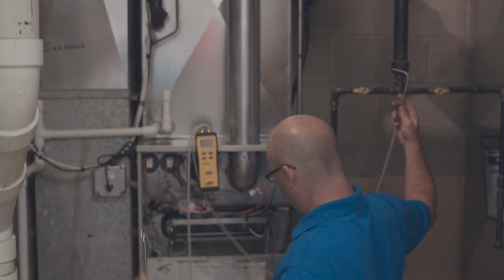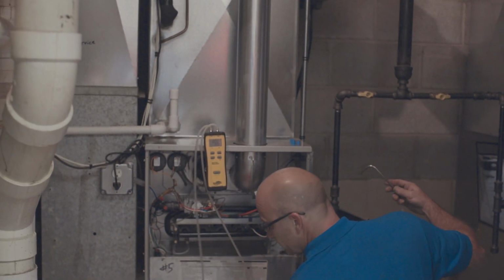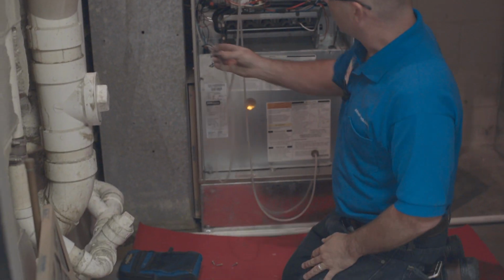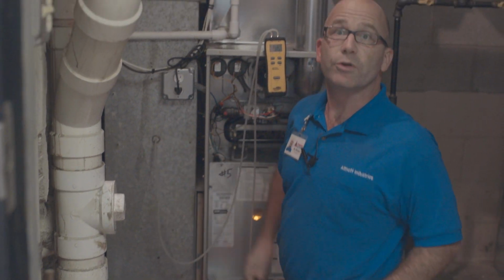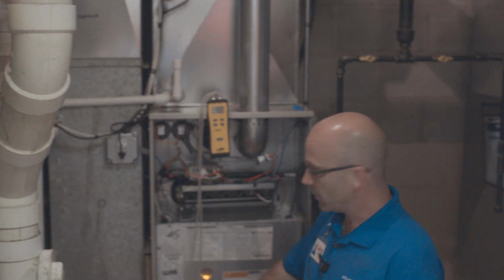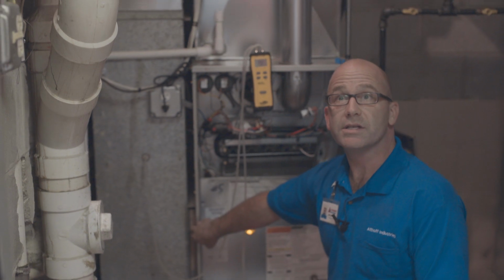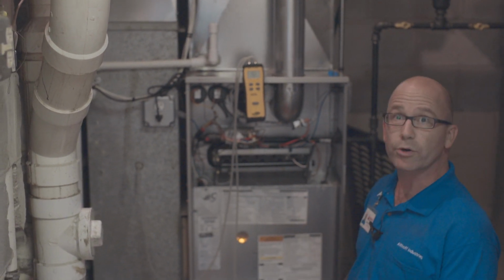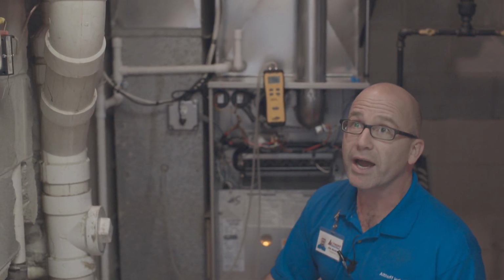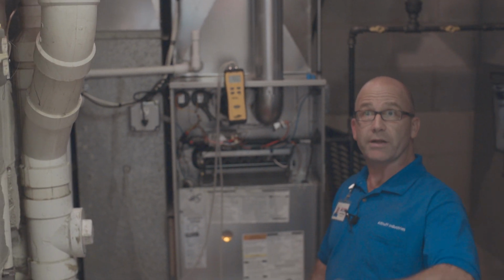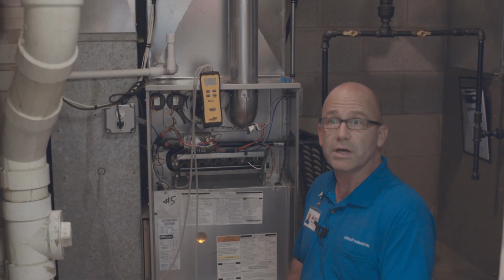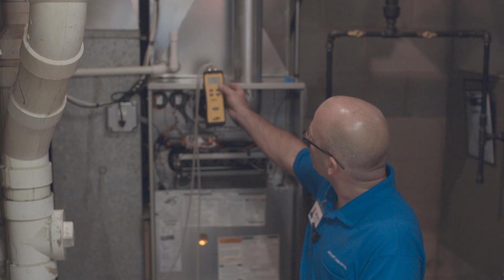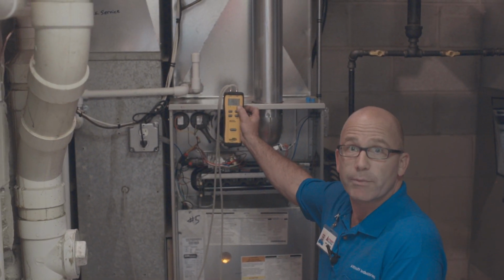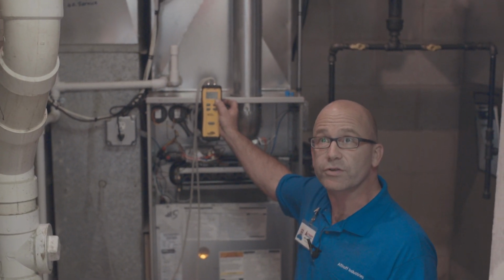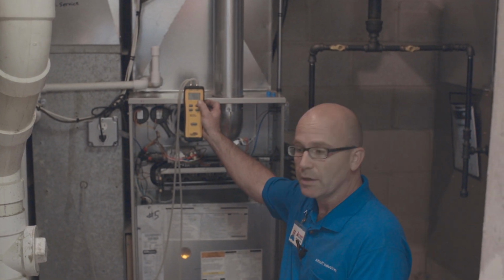I am going to put this static pressure tip in the return, and then I'm going to put this one in right here. The reason I'm doing a before and after, guys, is the filter right here is in between this probe and this probe. So I'm seeing what kind of impact a filter has on the system, meaning the higher the number, the worse situation it's going to be. So this bottom number right here on this manometer is the impact the filter is having, meaning the resistance.